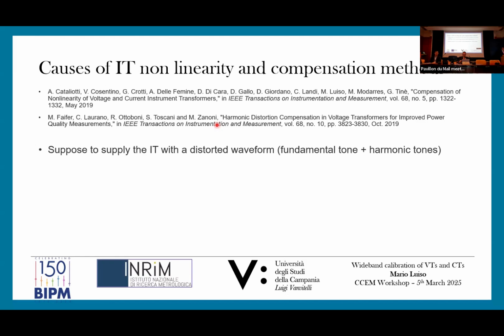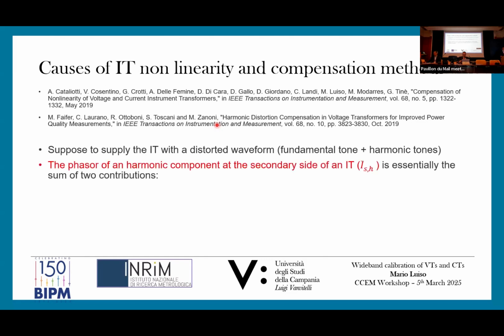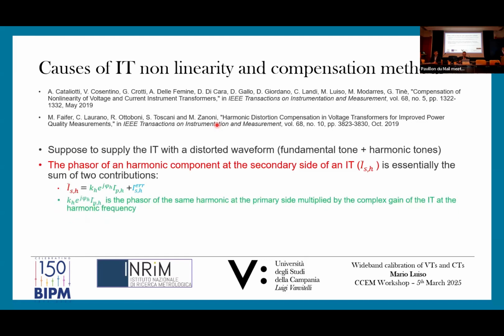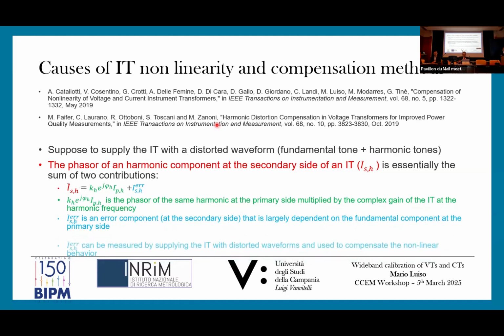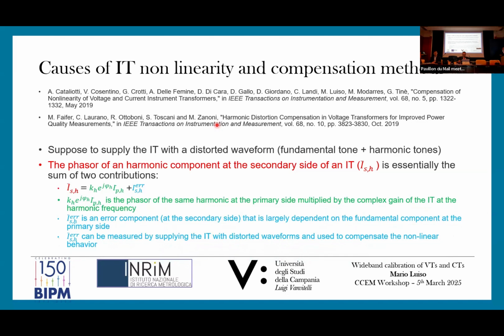So, suppose we supply the instrument transformer with a distorted waveform, fundamental tone plus harmonic tones. The phasor of a harmonic component at the secondary side of the instrument transformer is essentially the sum of two contributions. The first is the phasor of the same harmonic at the primary side of the transformer multiplied by the complex gain of the instrument transformer at the harmonic frequency. And the second is an error component that is largely dependent on the fundamental component at the primary side. This error term can be measured by supplying the instrument transformer with distorted waveforms and can be used to compensate the nonlinear behavior of the inductive transformer.